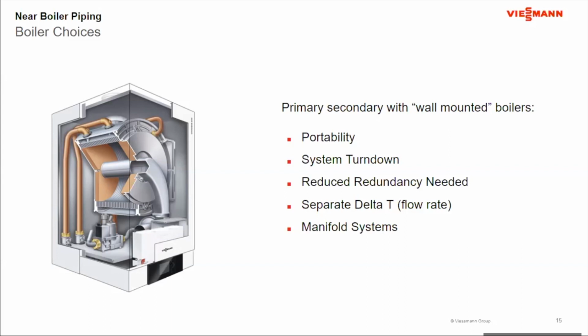All of a sudden, my redundancy becomes another 1 million BTU boiler. If I'm doing the wall-hungs at 500,000, the redundancy becomes another 500,000, so now I'm at 1.5 million versus the 2 million. And at that point, by the way, the footprint's also smaller. Okay, I can separate the flow rates and the delta T's. So all of a sudden, my system flow rate and my boiler flow rate don't have to match. The other big advantage of going with this style of boiler is there are manifold systems available that simplify the installation, even though I'm maybe doing an extra boiler or two by going to the wall-hung boiler.